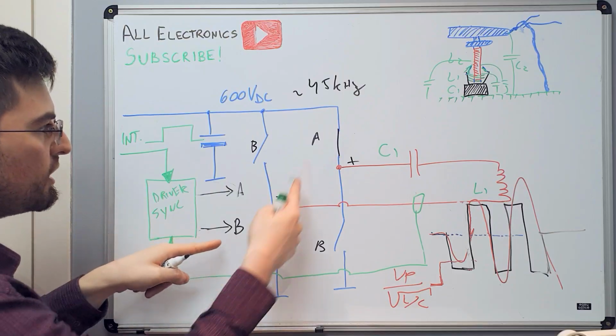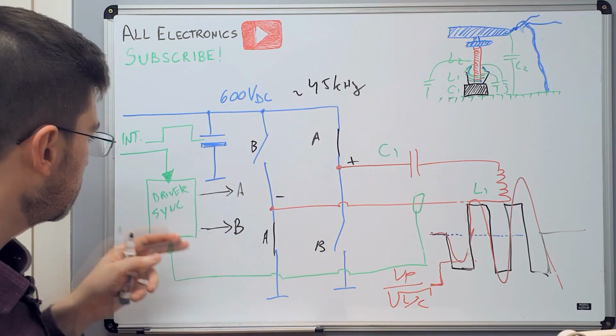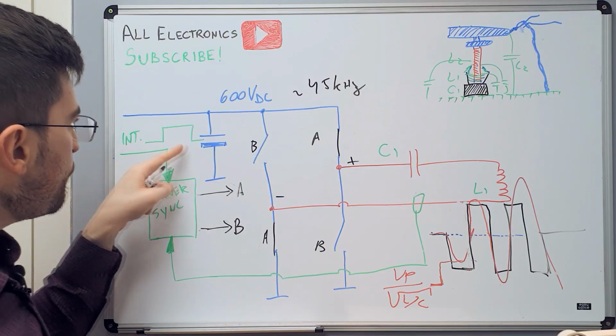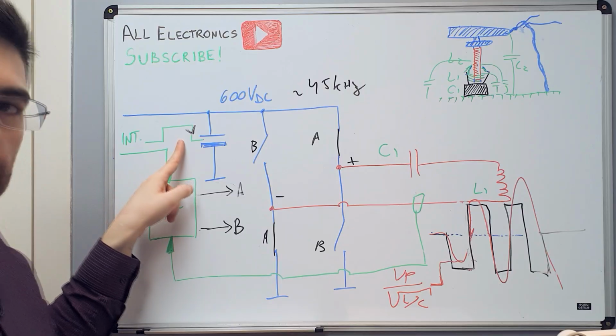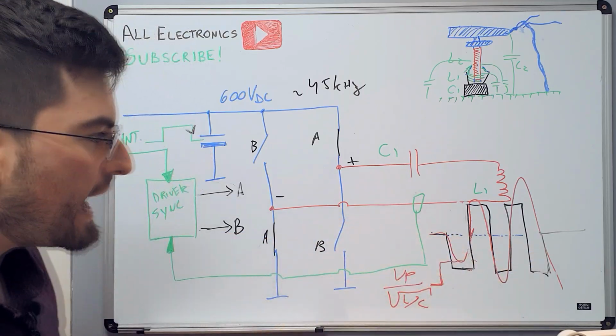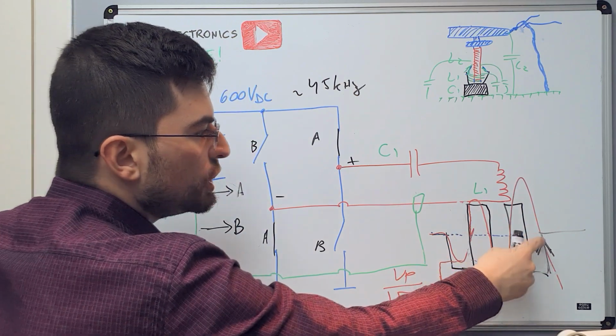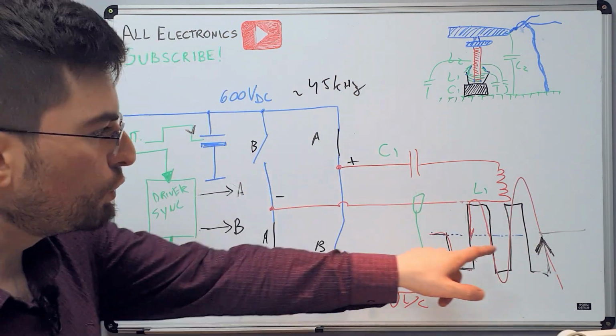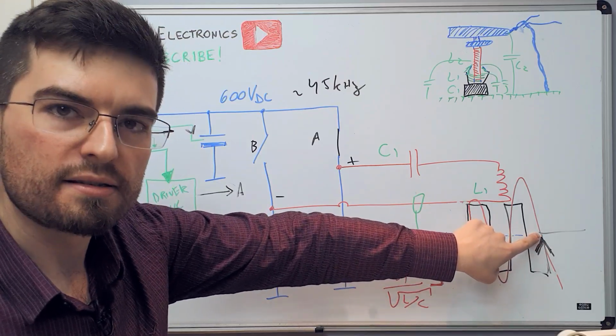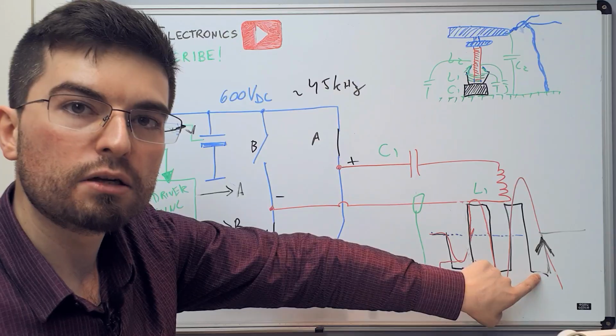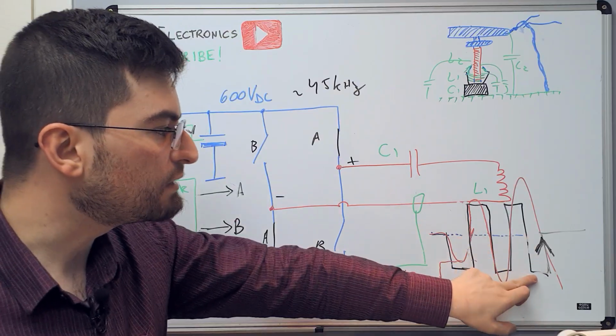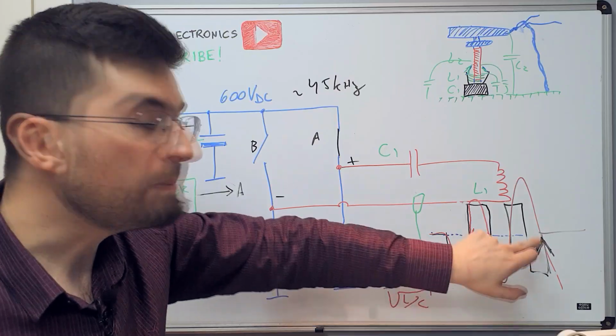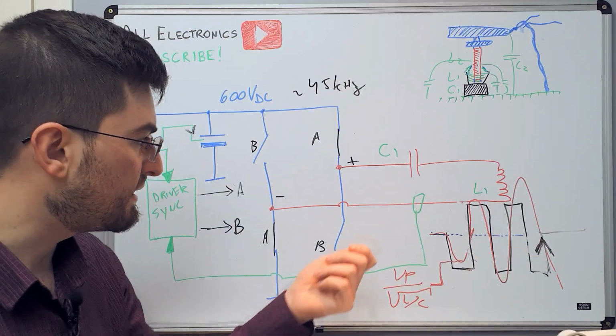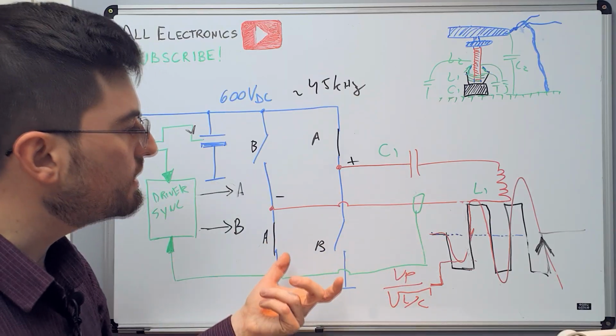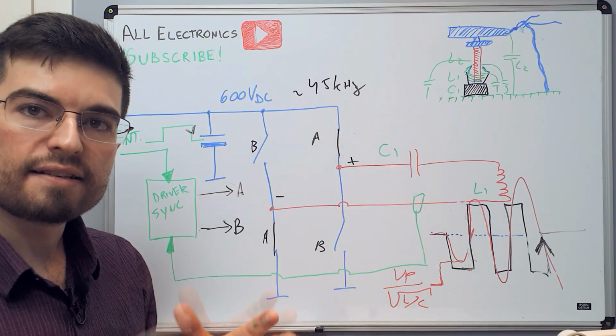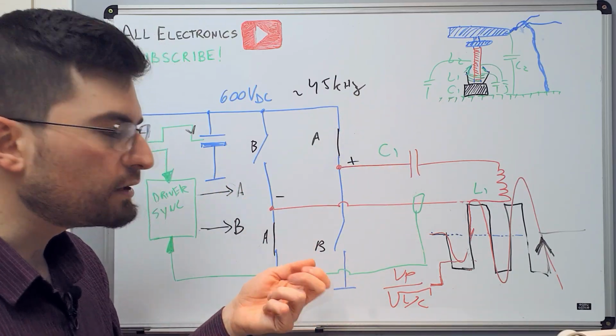The driver here, controlling the transistor, also has some synchronization logic. If we have a fall edge of the interruption, the drivers wait for the next transition here to switch in a zero current switching condition, switching only when the current crosses zero, not turning off the cycle in the middle of a half wave, preventing cutting these very high current profiles in the middle. This topology is very clever because it's self-resonant, it keeps track of the resonant frequency as it changes, but it also has a very important aspect: it works in soft switching.